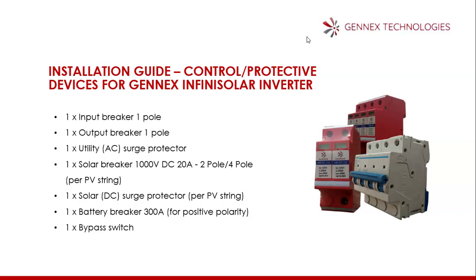Okay, so 1 utility AC surge protector, which is 3-pole. 1 solar breaker, 1000 volt DC 20 amps. It's either 2-pole or 4-pole. It's a special breaker, per PV string.